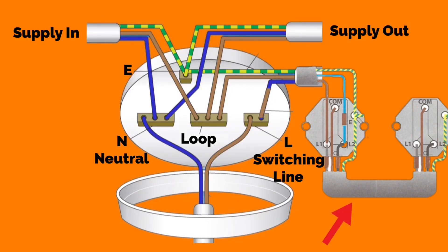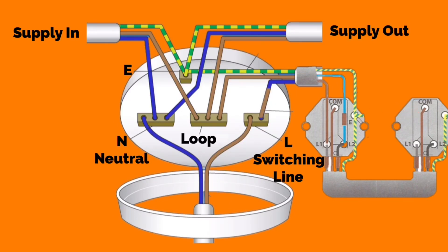The three-core and CPC cable links together L1, L2, and common of the first two-way switch across to L1, L2, and common of the second two-way switch. It doesn't matter which colors are used in which positions, however I like to use black as common. It doesn't matter if your L1 and L2 in the first switch are in L2 and L1 the opposite way around in the other, as long as the common cable remains the same - so if you've chosen brown for common in the three-core cable, it must be in the common terminal of the second two-way switch.